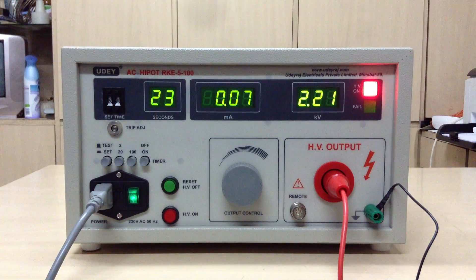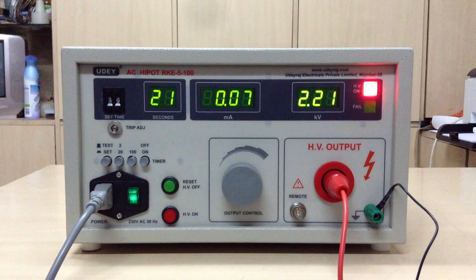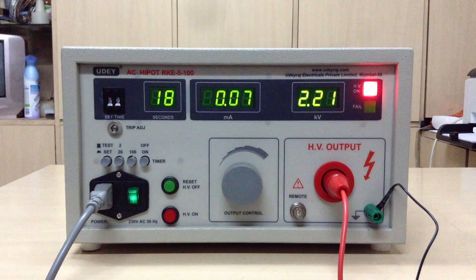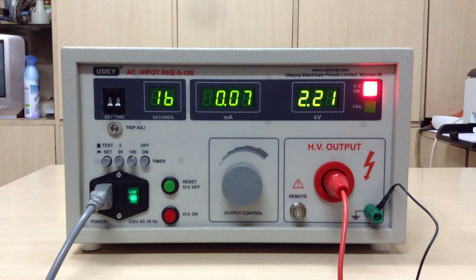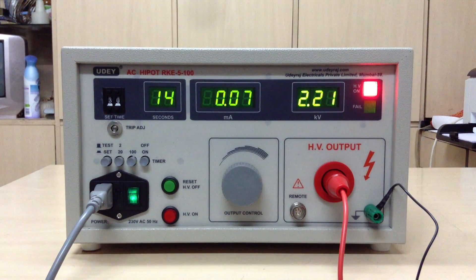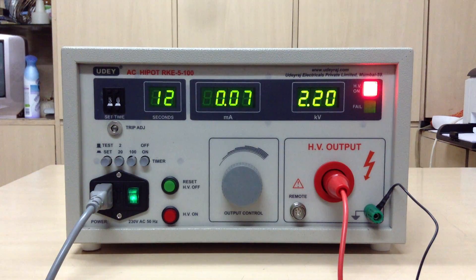You can see the leakage current on the display and it is a very compact and simple unit. Here you can see the HV ON indication coming and the seconds is counting there, and you can see the kV, mA, and seconds - everything.